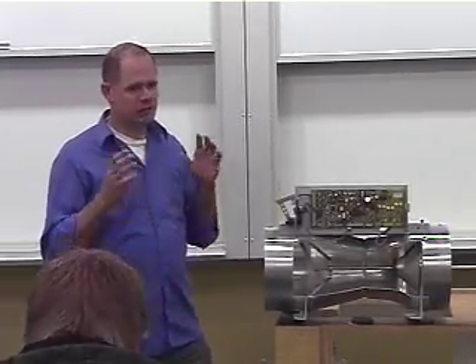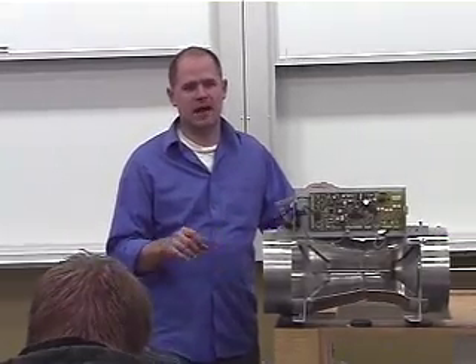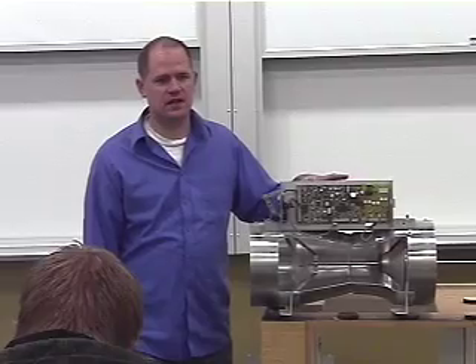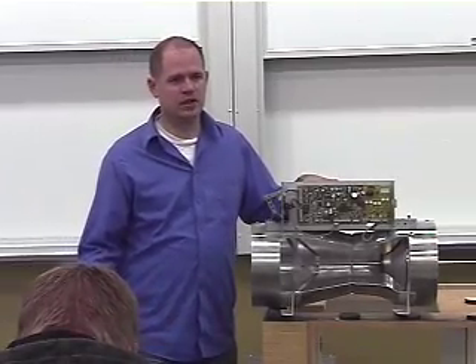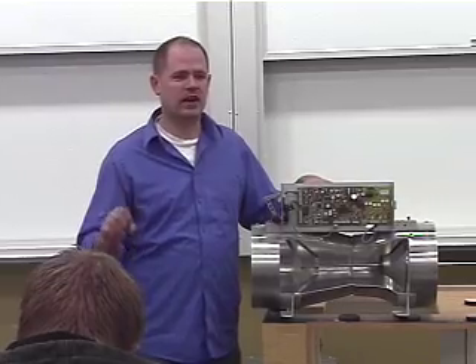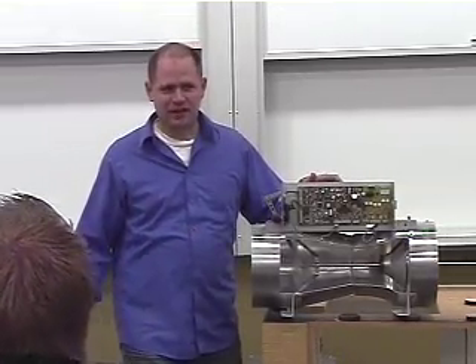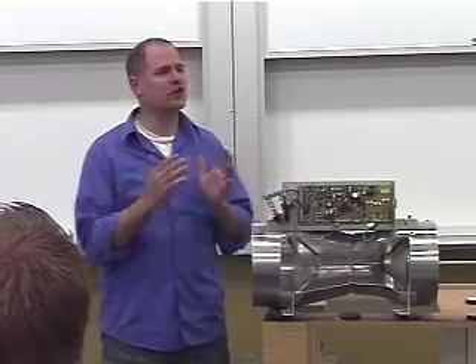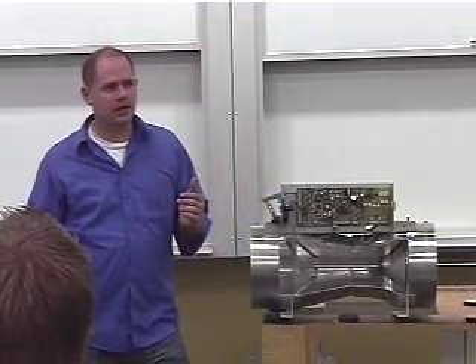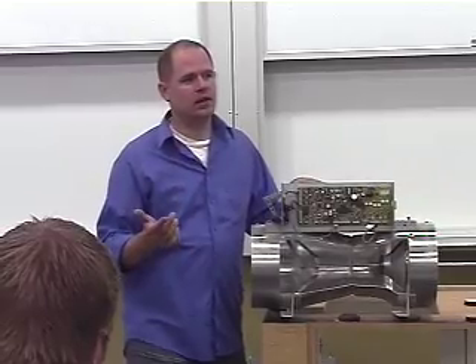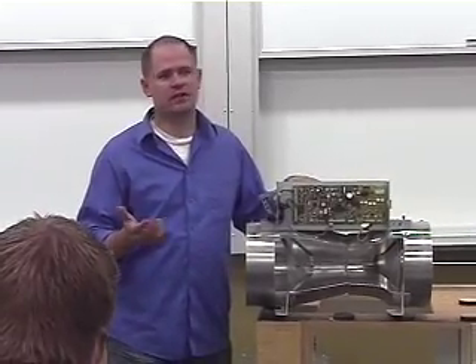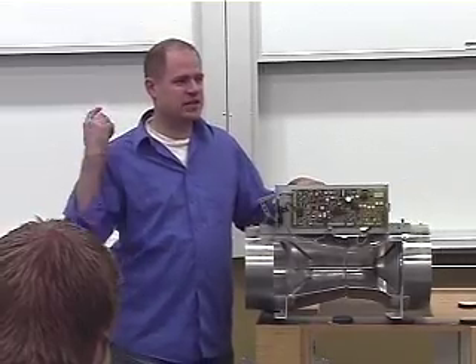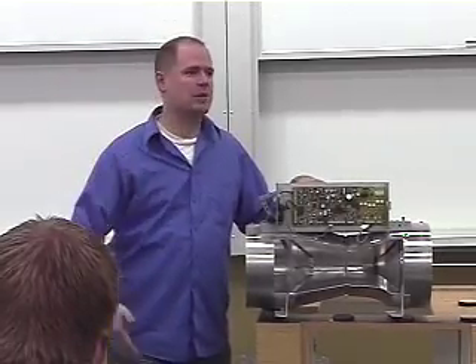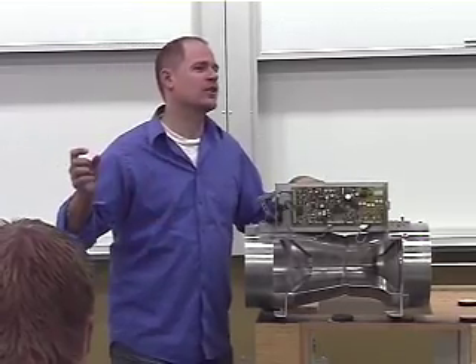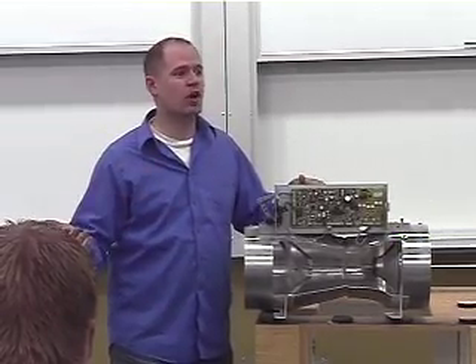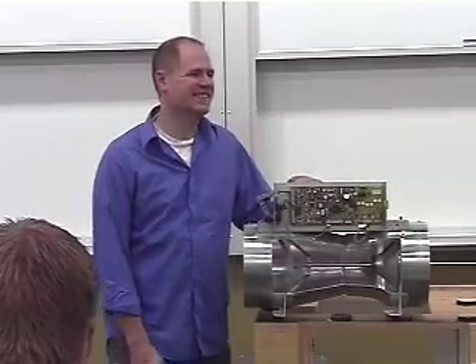The fail in place ones have fewer capacitors because they just have enough capacitors to make the damper move back and forth as it needs to. If it's a fail in a specific position one, it'll have additional capacitors because it needs to store enough energy so that if power goes out, it can go to fully closed or fully open or wherever you wanted it to fail to. Typically with a hood, in a failure mode, a fume hood, they want it to fail fully open so that it gets as much air out of there as they can. And you know your laminar flow is not correct on the hood, and then you get an alarm on the hood, so you know it's not the safest thing, but it's more exhaust than not.